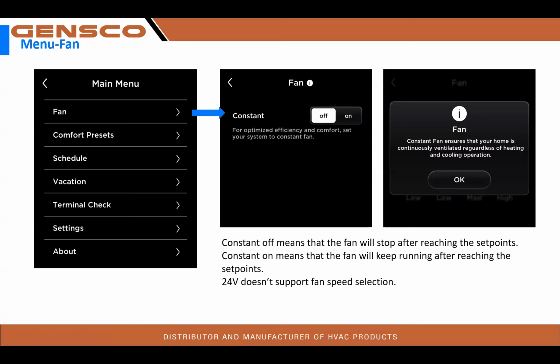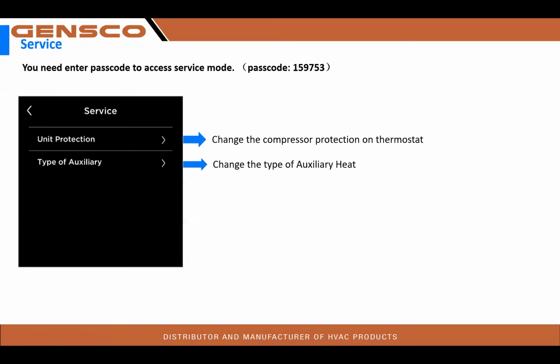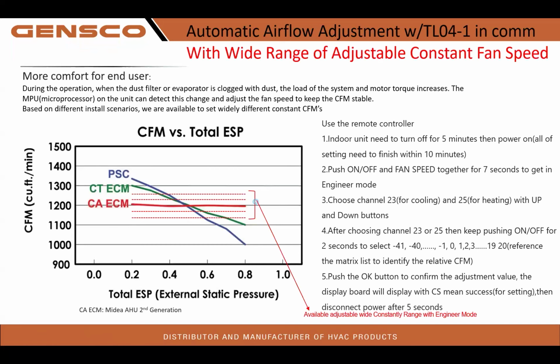Now we're back to the main menu for our 24-volt control. We can go constant fan on or off, set our schedules, vacation, settings, and about. Once again, to get into the service mode, our password is 159753. Settings and scenarios.